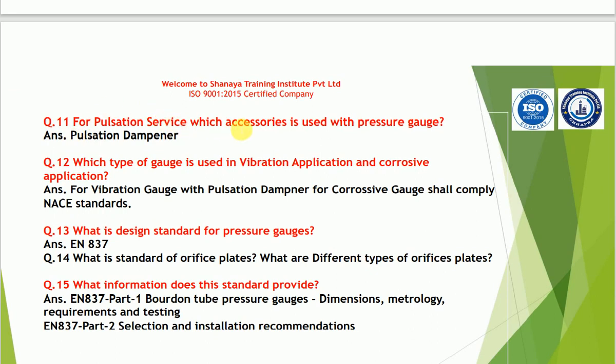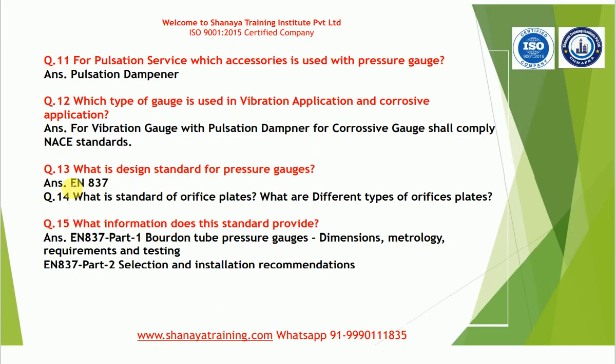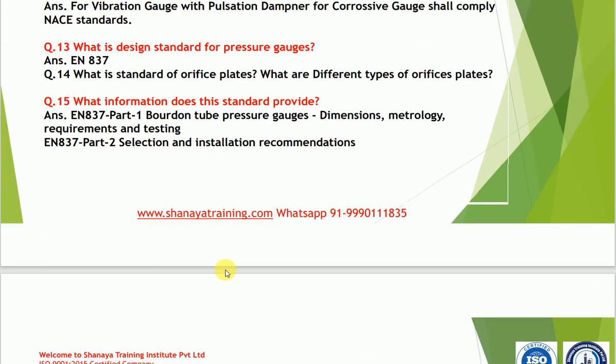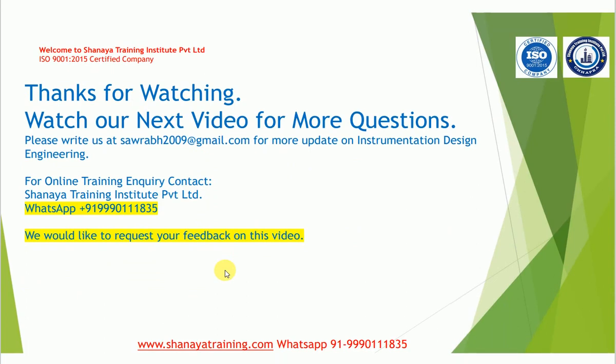For pulsation services, a pulsation dampener is used with the pressure gauge. For vibration applications, use a vibration gauge with pulsation dampener. For corrosive applications, a diaphragm seal shall be applied. The design standard for pressure gauge is EN837. EN837 Part 1 covers Bourdon tube pressure gauge dimensions, metrology requirements, and testing. EN837 Part 2 covers selection and installation recommendations.